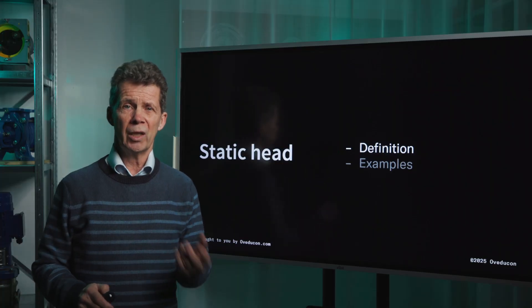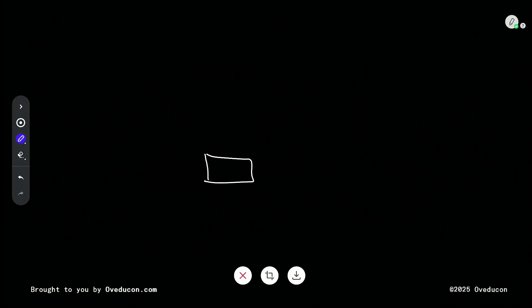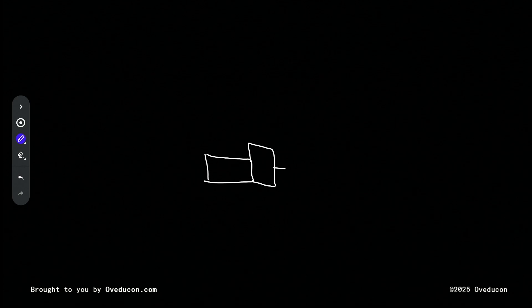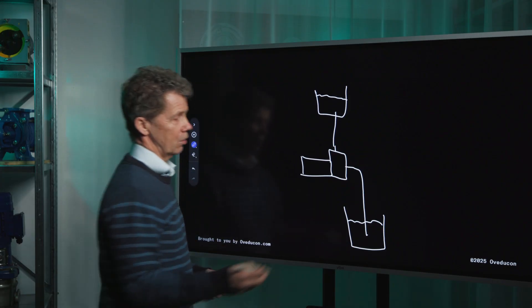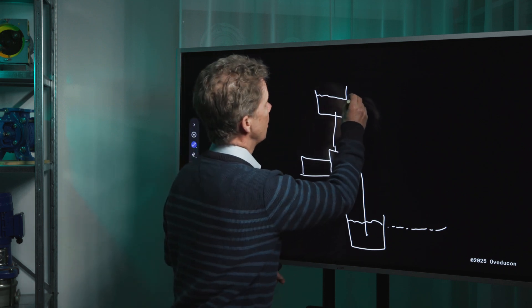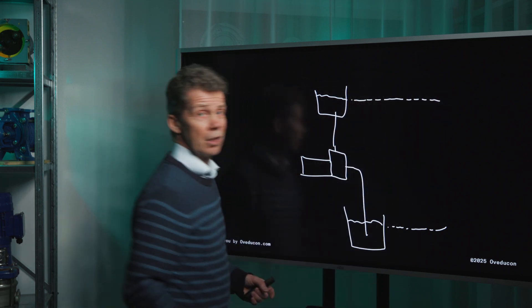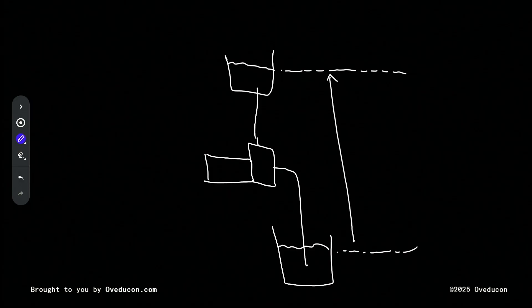I will show you in a very basic drawing. First I draw the pump, motor, pump house, suction port, discharge port, suction line, your suction tank with the medium level, discharge line, discharge tank, and medium level. To determine the static head we draw a horizontal line from the medium level in the suction tank to the medium level in the discharge tank. For this situation, your static head is this distance.